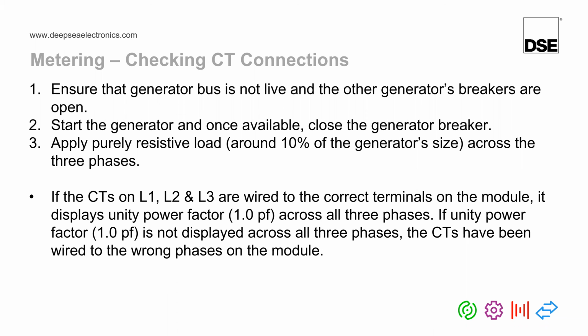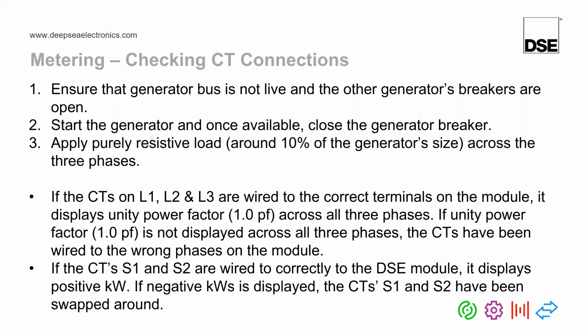So when we're doing the tests, what we're looking for are the following issues. We first need to check that all three phases, when using a purely resistive load bank, are at unity power factor, a power factor of 1. If a power factor of 1 is not displayed across all three phases, that suggests that some of the CTs are on the wrong phase. For example, maybe the L1 CT has been wired to L2 and the L2 CT has been wired to L1. If all the power factors are correct, but the kilowatts are being displayed as negative, then this suggests that the orientation of the CT or the S1 and S2 connections of that CT are the wrong way around.